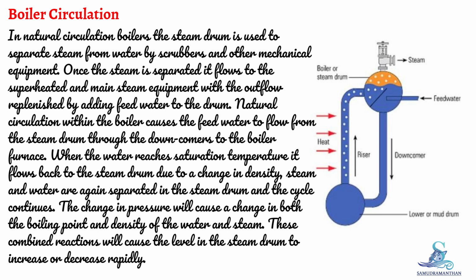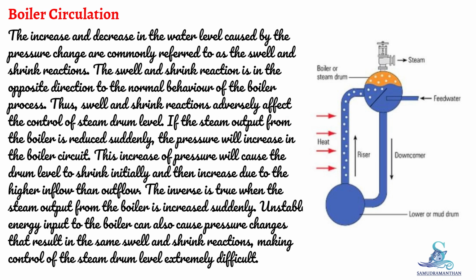The change in pressure will cause a change in both the boiling point and density of the water and steam. These combined reactions will cause the level in the steam drum to increase or decrease rapidly. The increase and decrease in the water level caused by the pressure change are commonly referred to as the swell and shrink reactions. The swell and shrink reaction is in the opposite direction to the normal behavior of the boiler process. Thus, swell and shrink reactions adversely affect the control of steam drum level.